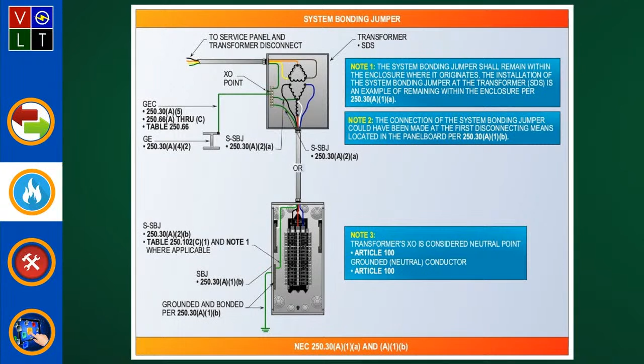All right. Now, this is another one, and this is sort of where I was talking about seeing how we redid the interior of transformers. You'll see us show some of the transformers this way. It depends if we're showing a connection or not. This is just one where we're showing a double fed, or basically double ended, type. And these are systems that are installed in accordance with 450.6. This is where you have a single system bonding jumper connection to the point of the grounded circuit conductors from each power source. And when you go over and look, it shall be permitted at this point for the separately derived systems that are double ended in a common enclosure, which employ what? A secondary tie. So in this kind of situation, what would you use this application for?